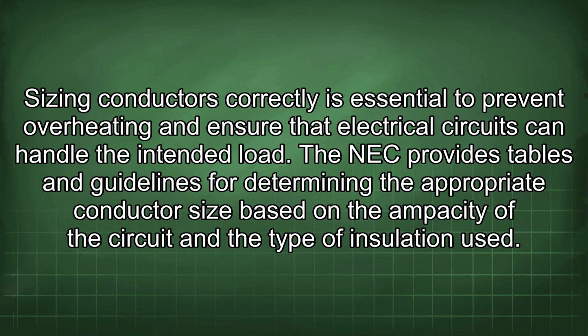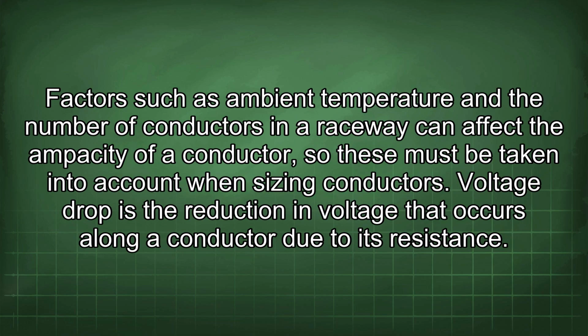Sizing conductors correctly is essential to prevent overheating and ensure that electrical circuits can handle the intended load. The NEC provides tables and guidelines for determining the appropriate conductor size based on the ampacity of the circuit and the type of insulation used. Factors such as ambient temperature and the number of conductors in a raceway can affect the ampacity of a conductor, so these must be taken into account when sizing conductors.